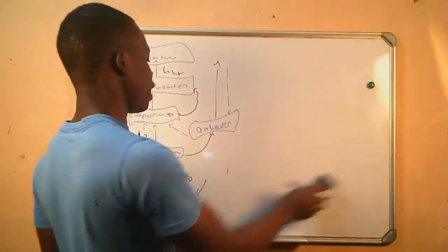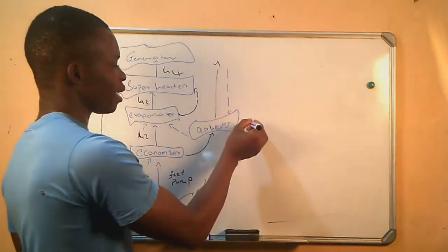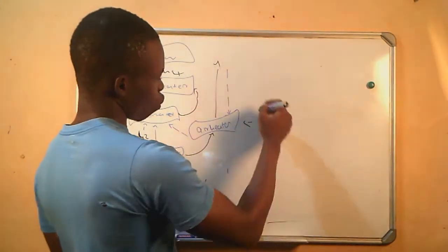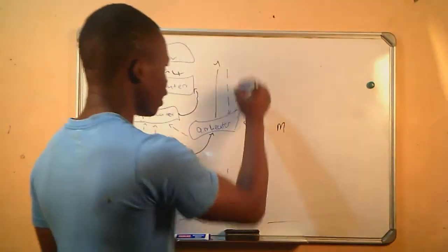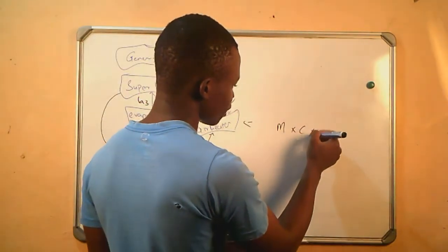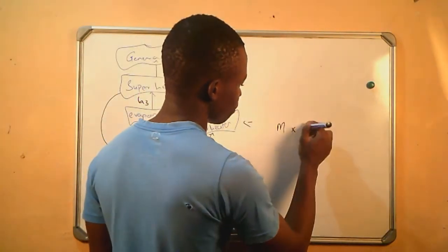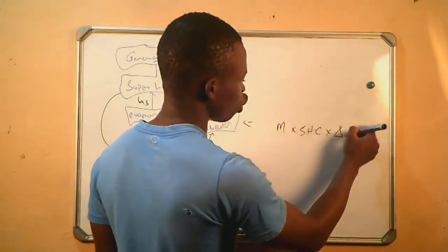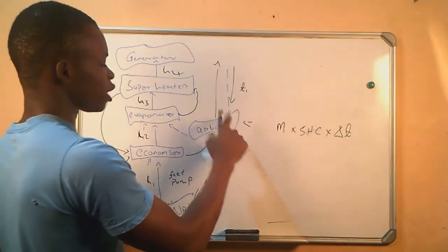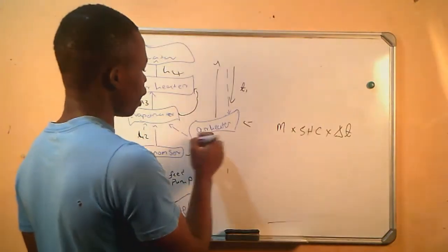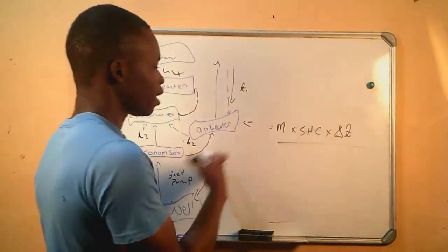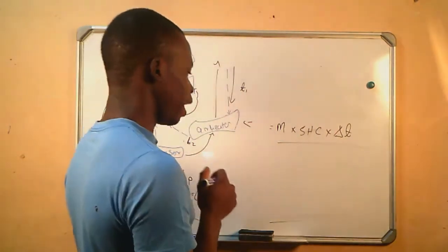Another component where heat is gained is the air heater. To calculate the heat energy that is gained there, you are going to say the mass of the air entering times the specific heat capacity times the change in temperature — which is the temperature of the air before the air heater and the temperature of the air after the air heater, T2. This gives you the heat energy that was transferred in the air heater.